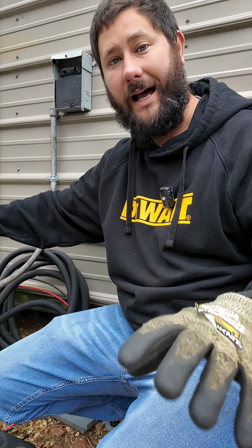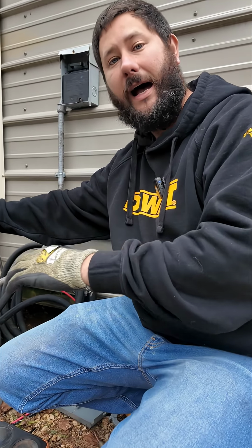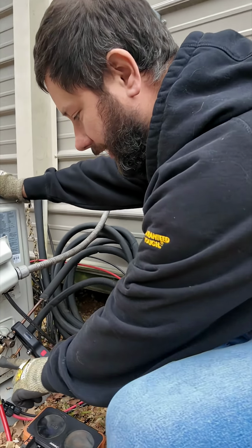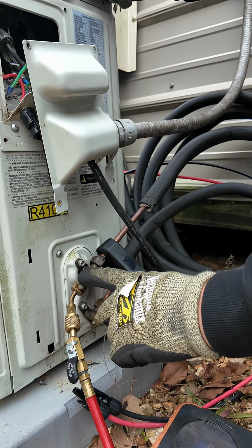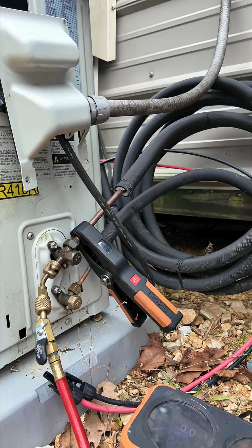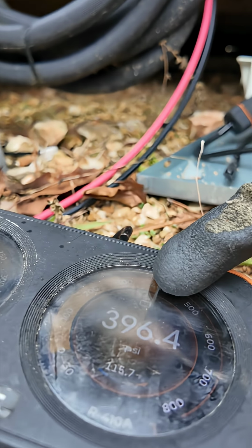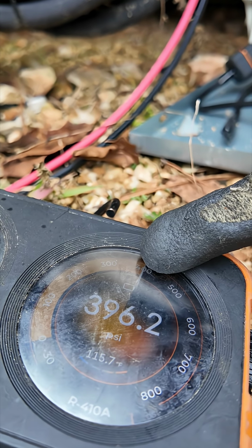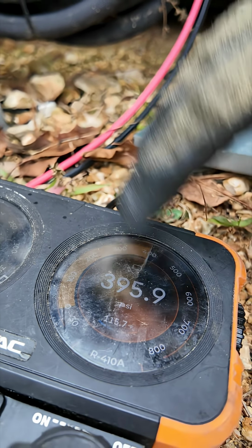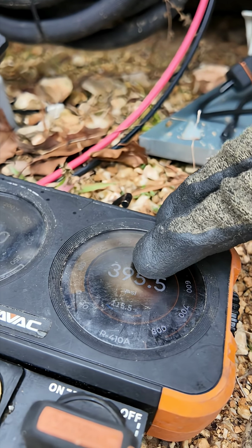We're at the outdoor unit. I've got my gauges connected. We're using the high side gauge, the red high side hose, and the 1/4 inch to 5/16 adapter so we can connect to our service access fitting. Look at the pressures. We're reading 396. And in the heating mode, you're going to have higher pressure than during the cooling mode.